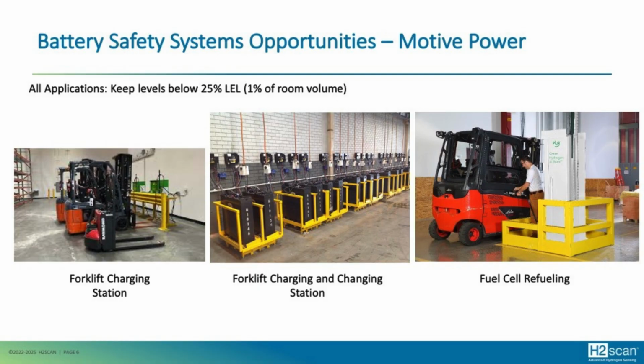And one thing I'll mention in any of these applications, and we'll also mention it later in this presentation, is the fact that hydrogen will confuse a carbon monoxide sensor. So if you have carbon monoxide sensors near the area and they happen to be going off, that could mean that it's actually reading hydrogen and not carbon monoxide. So then you would have to have both sensors to figure out whether it is hydrogen or carbon monoxide, because carbon monoxide sensors are very basic TCDs or MOS sensors that can't distinguish between hydrogen and carbon monoxide. They just know that there's a toxic gas there.